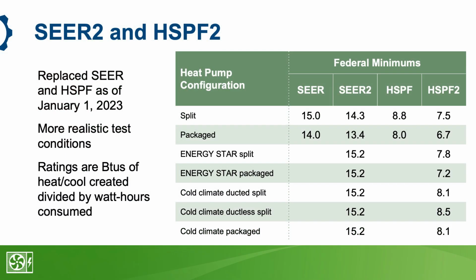Because the federal incentives refer to it, let's take a minute to cover one important technical detail regarding how we talk about the efficiency of heat pumps. As of January 1, 2023, SEER 2 and HSPF 2 are the new efficiency metric standards for heat pumps. The main difference between the old and the new ratings are the testing conditions for each of those rating systems. The new testing conditions will produce different data values, and they warranted a new rating system. So for SEER 2 and HSPF 2 ratings, the testing procedure increases the pressure conditions to make them more like what you'll see in an actual ducted system in the field.